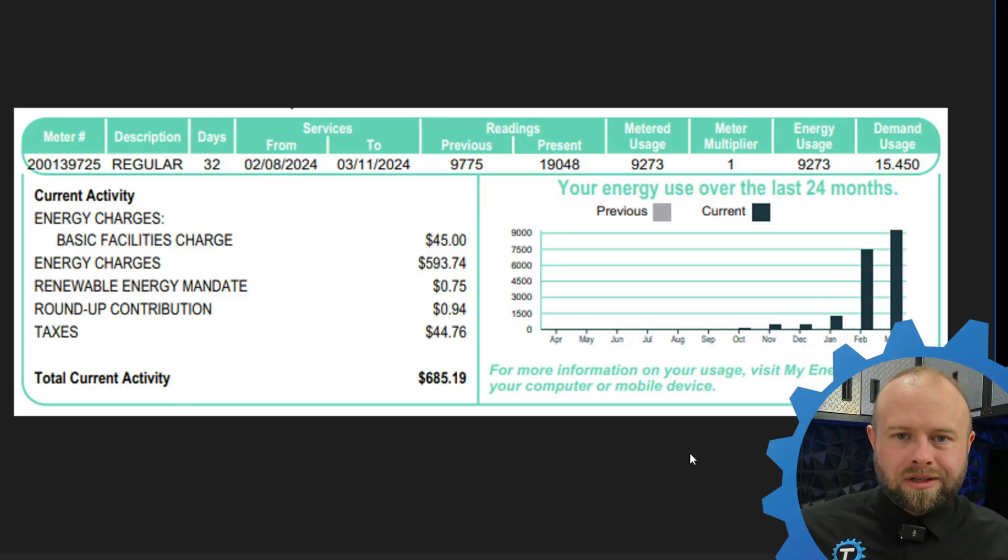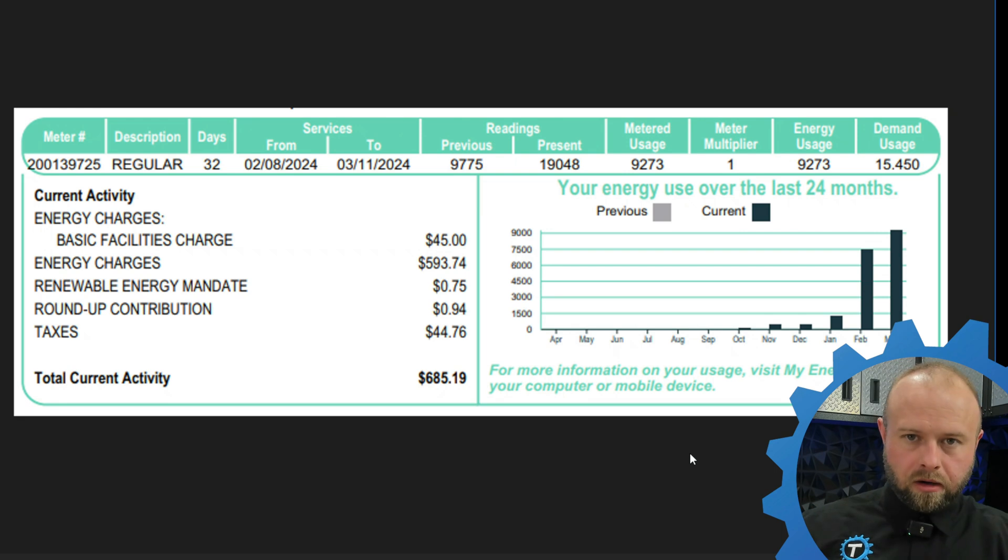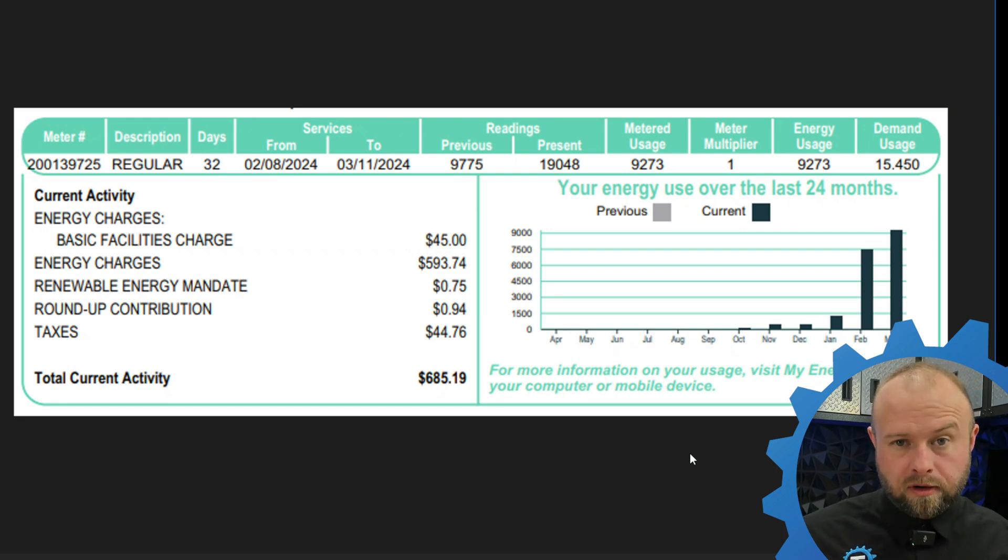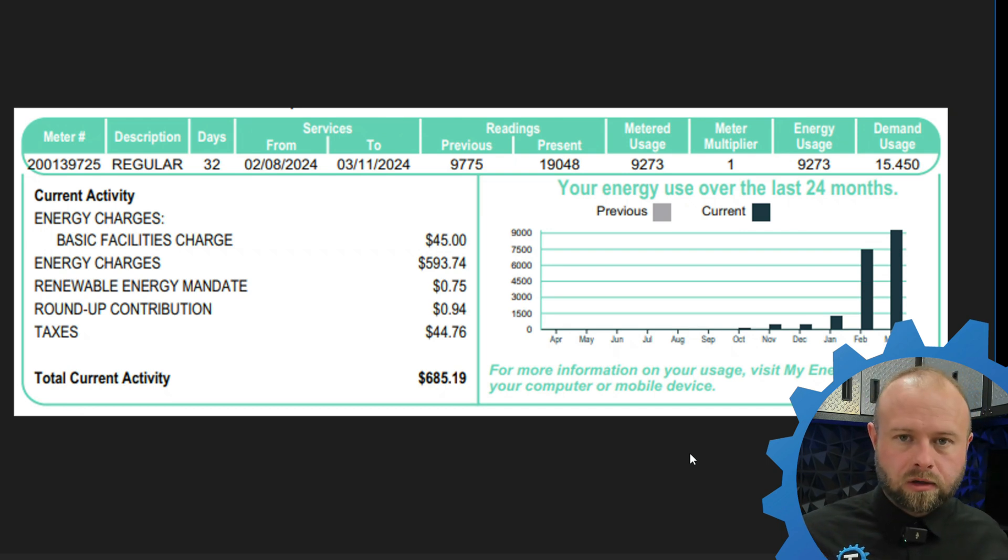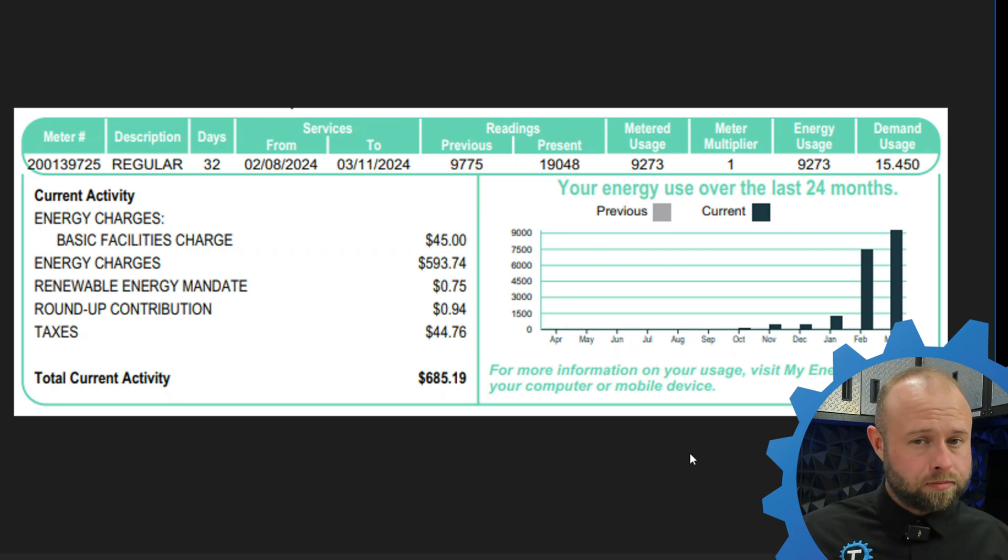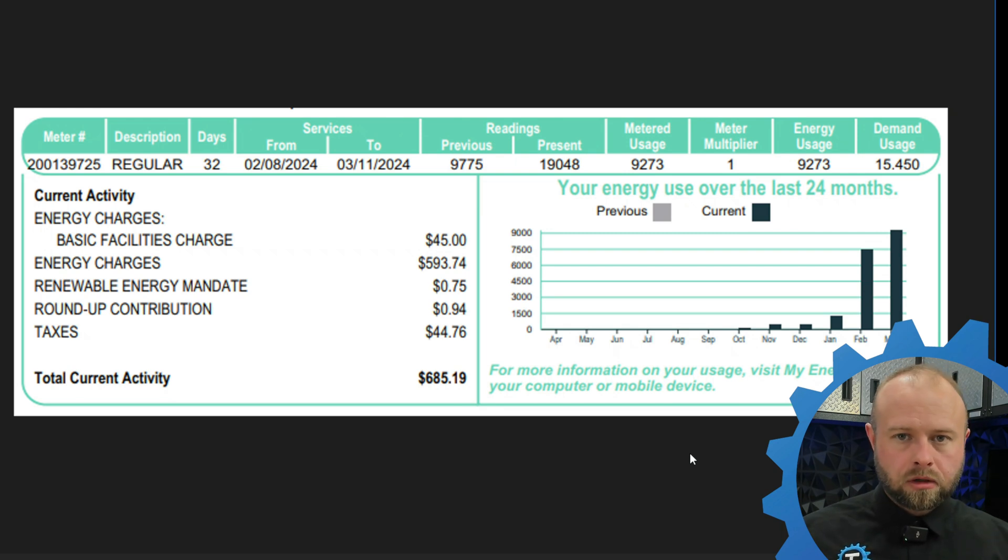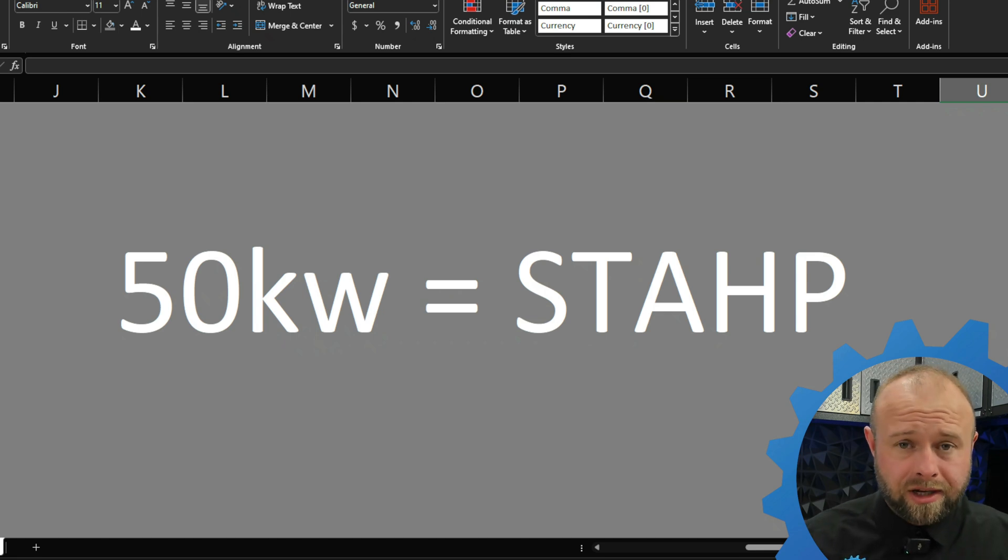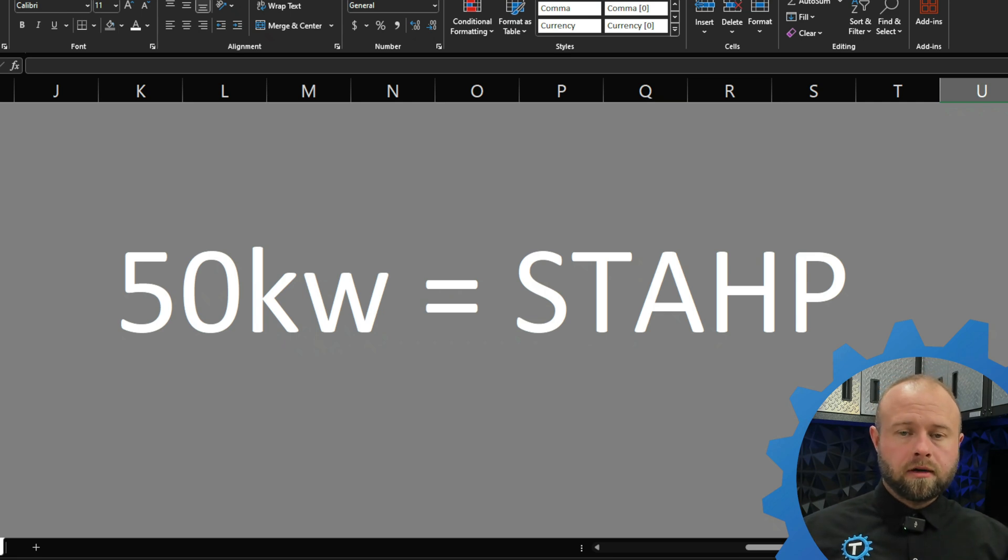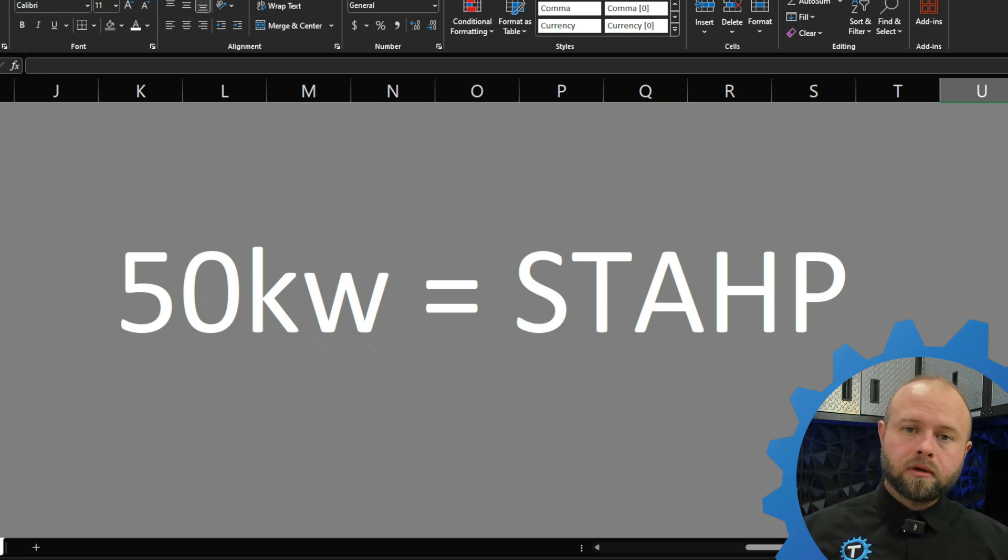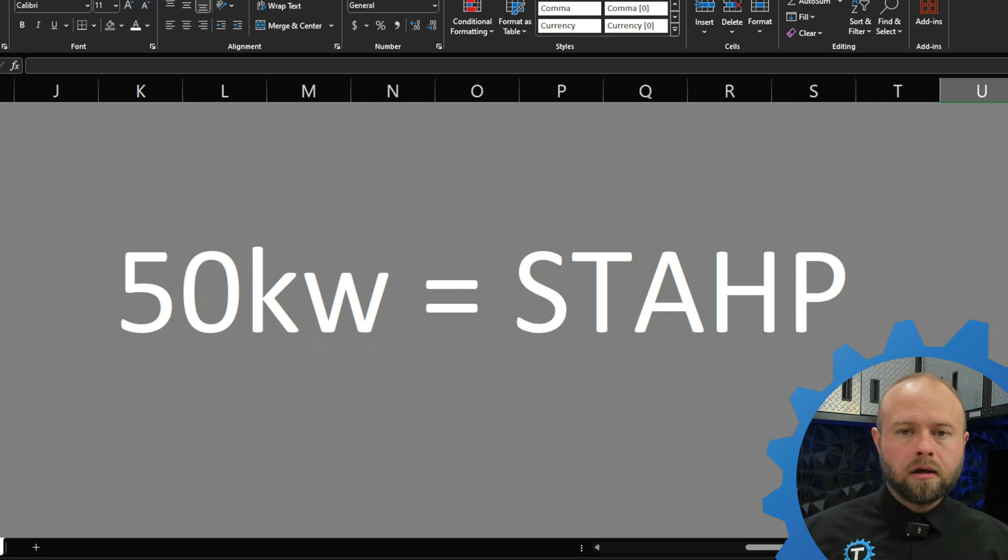And so ultimately I was right. I should never doubt myself. I'm always right because it was the meter that was the problem. The time change, something with the firmware, the meter thought that two hours worth of time became one instant of time and the meter registered me as using 70 kilowatts of power all at once when that was clearly not the case. So I'm in the clear, but the most important thing I learned from this entire exchange is what the threshold is for demand charges. And that threshold is 50 kilowatts. I could not find this information anywhere in their online documentation. I had to speak to the engineer to get this information.